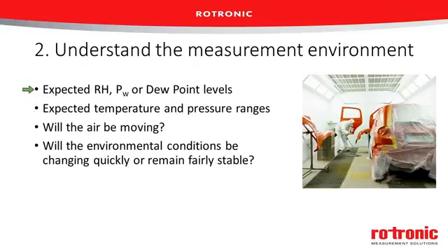Number 2 is to understand the environment which you're going to be measuring in. And this is more important for the extreme conditions, but it's a best practice to really answer these different parameters. For example, what's the expected relative humidity range? Will it be just between 20 and 40%, or will it be an entire range from 0 to 100%?